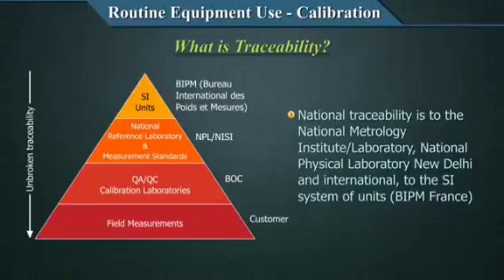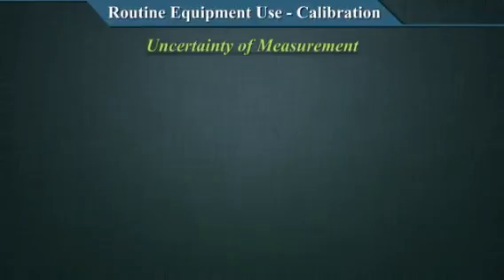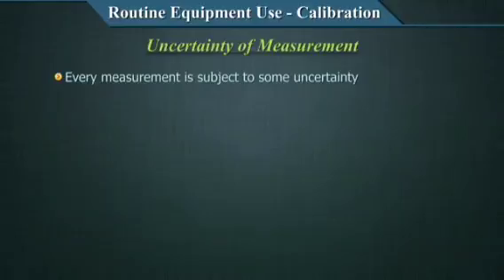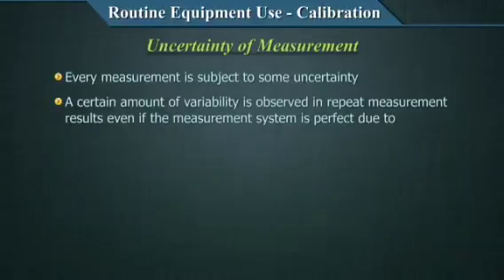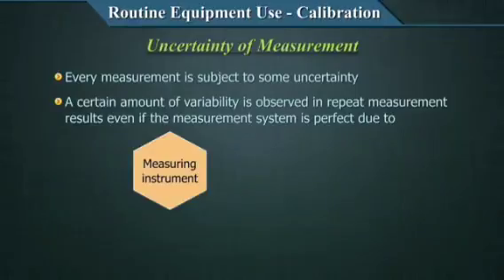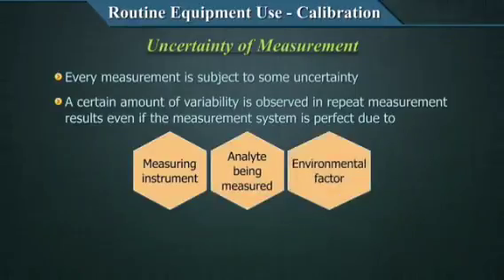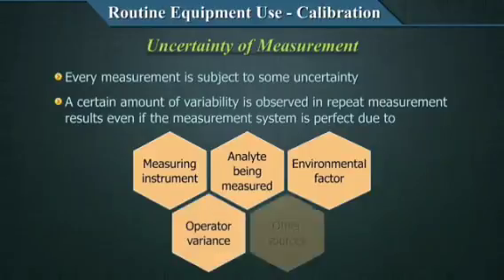After traceability, the second concept that requires mention in the case of calibration is the uncertainty of measurement, something that we need to understand in detail. Every measurement is subject to some uncertainty, even the SI units. A certain amount of variability is observed in repeat measurement results even if the measurement system is perfect. This is an inherent characteristic of a repeat measurement, and this can be due to the measuring system, the analyte being measured, the environmental factors, the operator variance, or other sources.